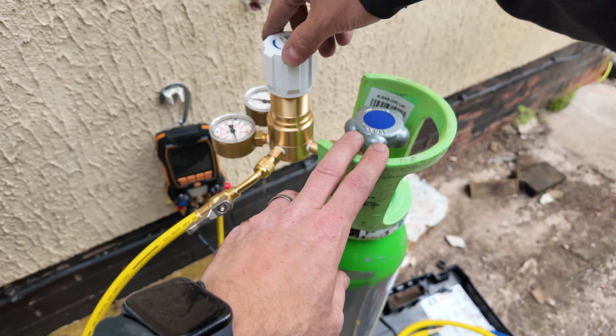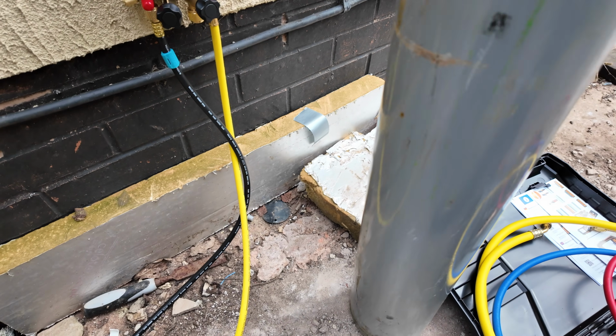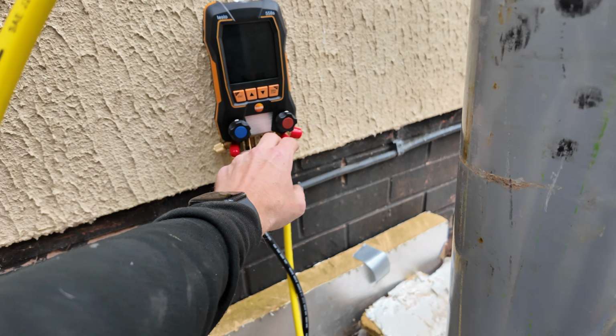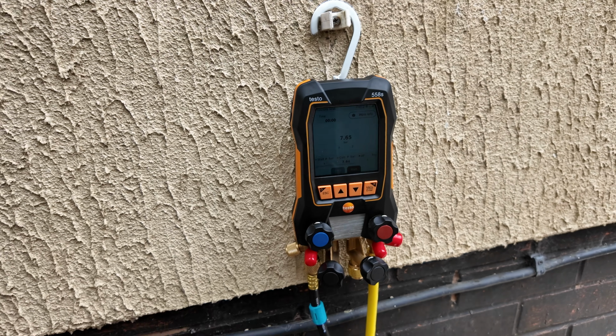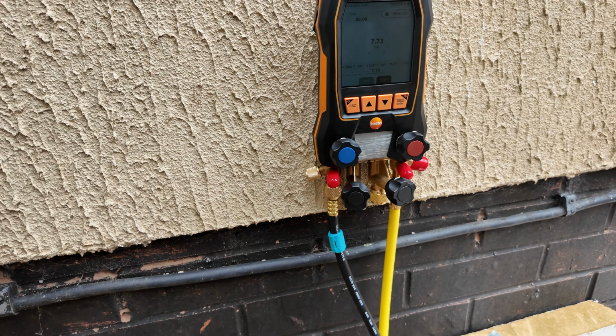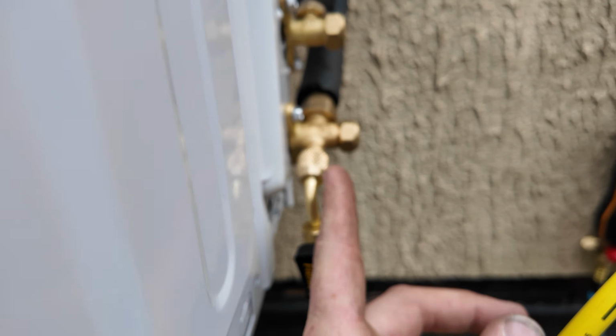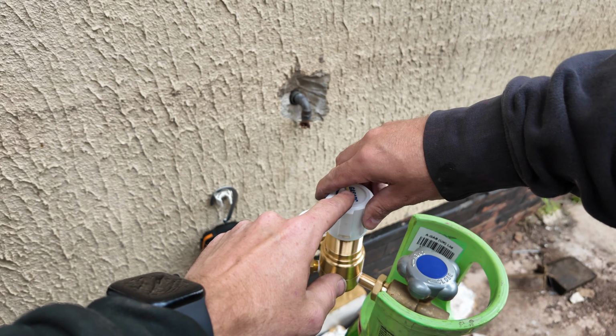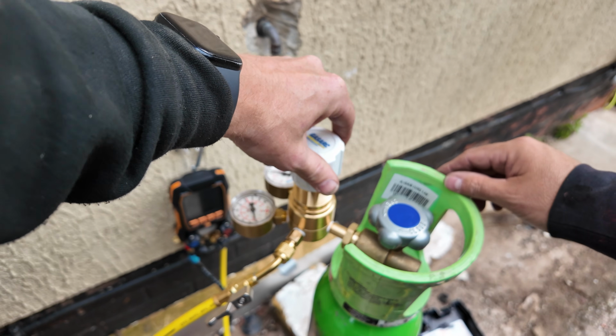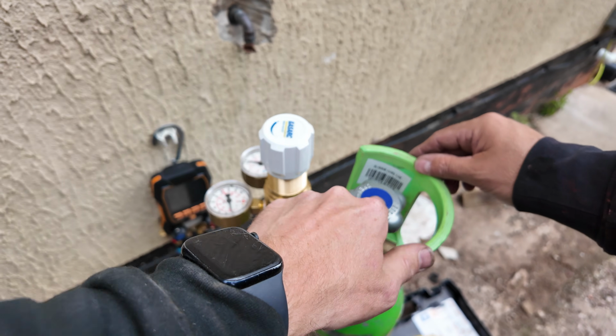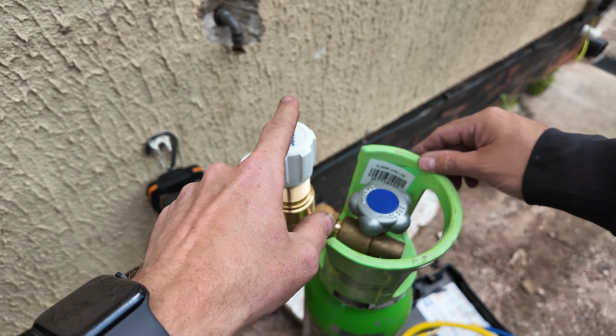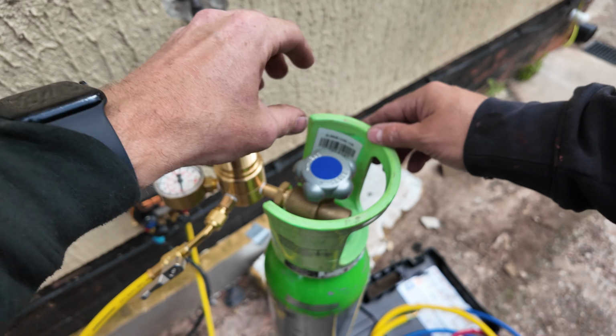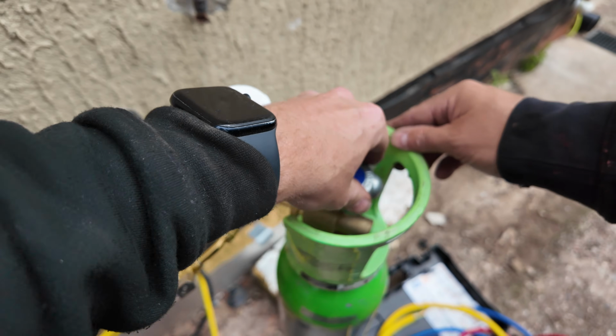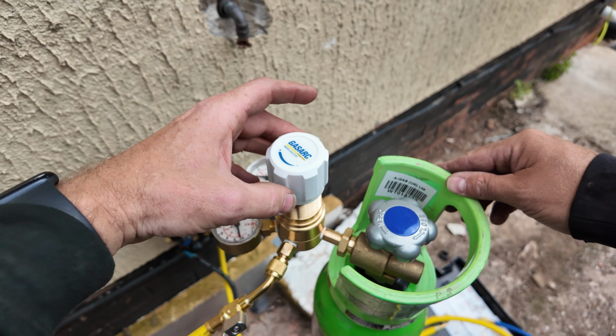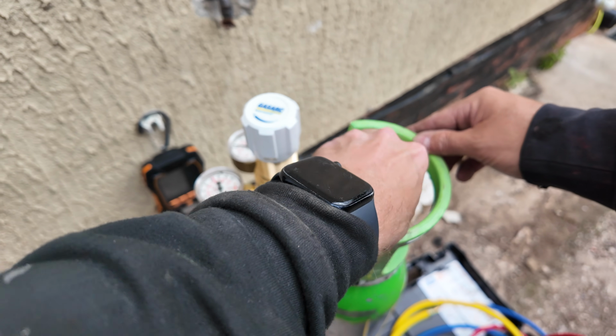So you've got the oxygen free nitrogen, with a hose going from the unit to the red port on the Testo - that's the Testo 558S. Then we've got another one coming out the blue port here, going up to the unit. When you first do it, make sure this is backed off on negatives, and open up your nitrogen bottle because that controls the pressure. Make sure that's open like that - sorry, make sure that's closed like that. That's what you've got to get your head around: opening is closing, closing is opening. So open that.